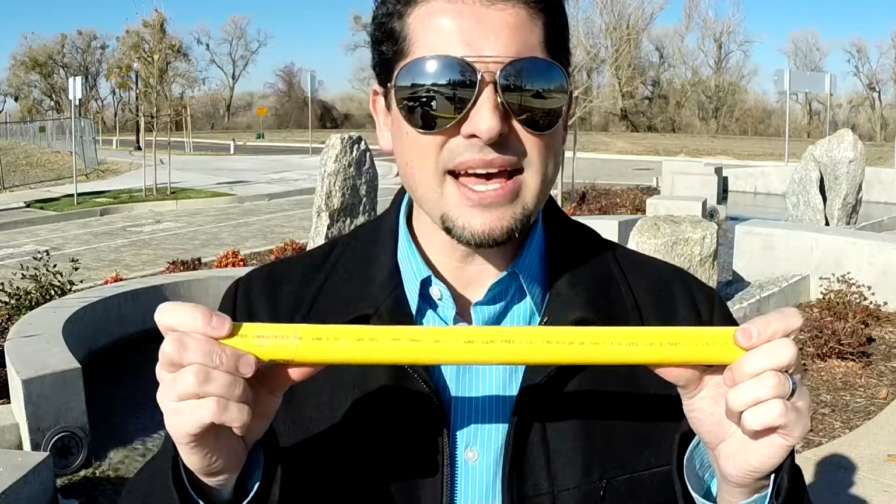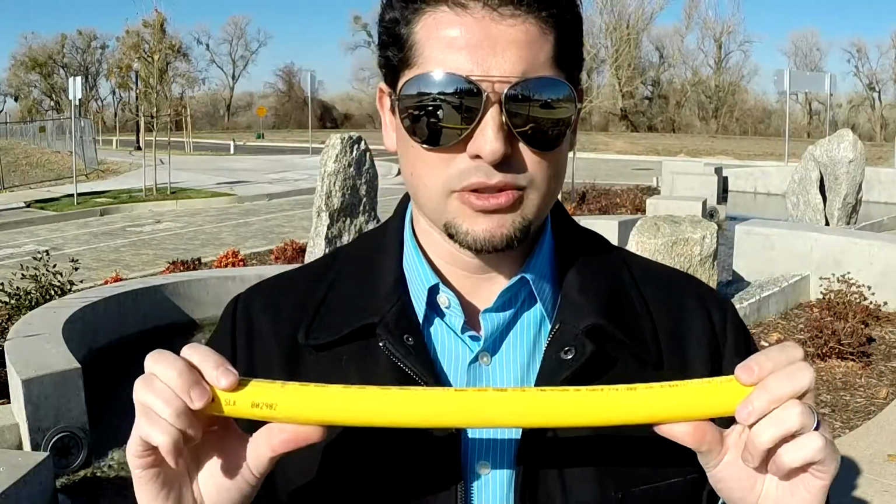The limit on ampacity of a cable is a thermal limit. This conductor can carry as much current as you want it to carry, but if it carries too much for too much time, it will exceed temperature ratings and the insulation will start to melt, or if it gets hot enough, the conductor itself can start to melt.